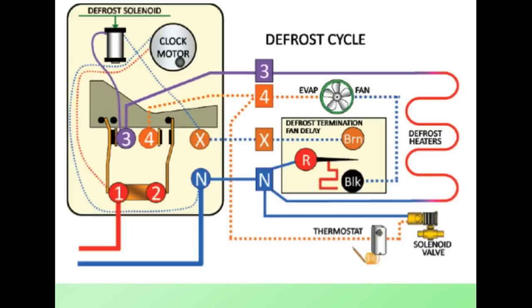Quick review of the defrost cycle. We're in the defrost cycle - clock motor's humming along, defrost solenoid has 115 volts but no neutral, evap fan has no power and is off, solenoid valve has no power and is closed, defrost heaters are on, and we are melting the ice off of the coil.